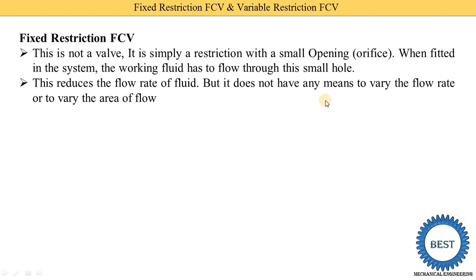It does not have any means to vary the flow rate or to vary the area of flow. In an orifice, a small fixed diameter is there, so we are not able to change this diameter. If we cannot change the diameter, then the area is not changed. We know that flow rate Q is equal to area multiplied by velocity. In any type of flow controller, we consider the velocity is constant. So by changing the area, we only change the flow rate. If we increase the area, flow rate increases; if we reduce the area, flow rate decreases. By using fixed restriction FCV, we are only able to reduce the flow rate.